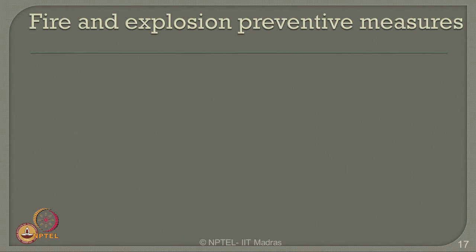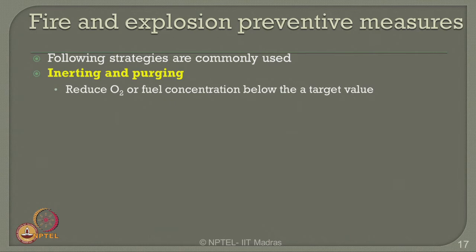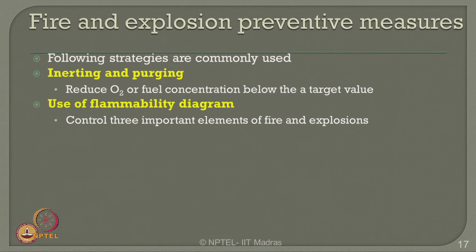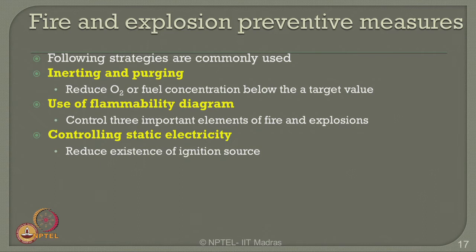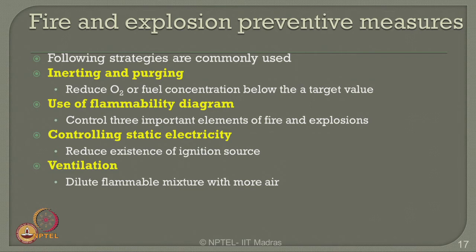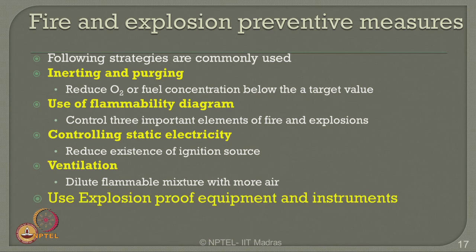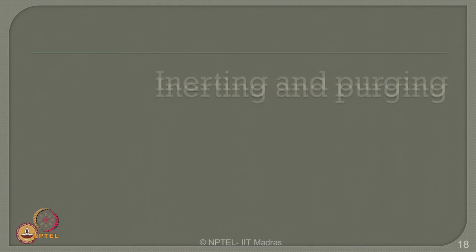Let us look at preventive measures commonly adopted in industry for preventing fire and explosions. The following strategies are commonly used: inerting and purging, which reduces oxygen content or fuel concentration below a specific target value; use of a flammability diagram to control the three elements of fire and explosion; controlling static electricity; reducing ignition sources; providing enough ventilation by diluting the flammable mixture with more air; using explosion-proof equipment; and using sprinkler systems.